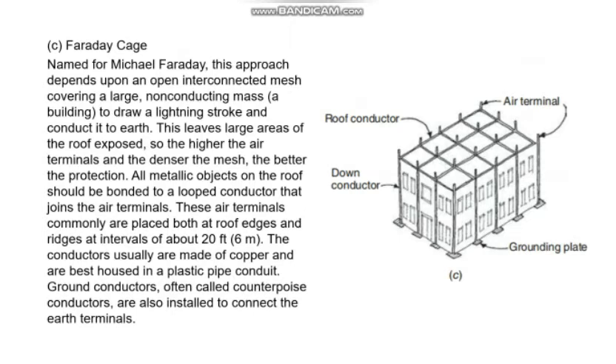Third example is the Faraday cage, named for Michael Faraday. This approach depends upon an open, interconnected mesh covering a large, non-conducting mass or the building to draw a lightning stroke and conduct it to earth. This leaves large areas of the roof exposed, so the higher the air terminals and the denser the mesh, the better the protection. All metallic objects on the roof should be bonded to a looped conductor that joins the air terminals. These air terminals commonly are placed both at roof edges and ridges at intervals of about 20 feet.